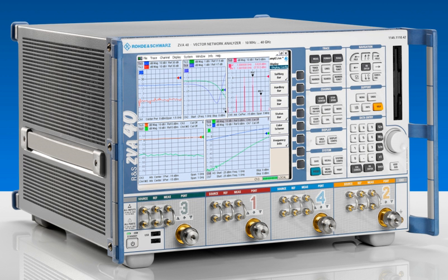Topic: receiver. The receivers make the measurements. A network analyzer will have one or more receivers connected to its test ports. The reference test port is usually labeled R, and the primary test ports are A, B, C. Some analyzers will dedicate a separate receiver to each test port, but others share one or two receivers among the ports. The R receiver may be less sensitive than the receivers used on the test ports. For the SNA, the receiver only measures the magnitude of the signal. A receiver can be a detector diode that operates at the test frequency. The simplest SNA will have a single test port, but more accurate measurements are made when a reference port is also used.